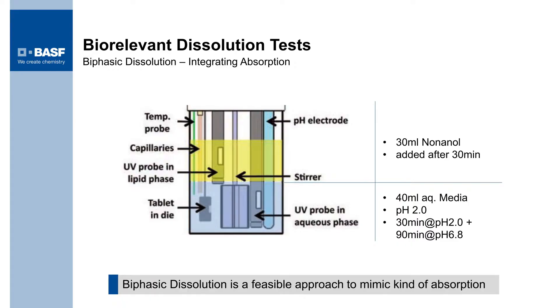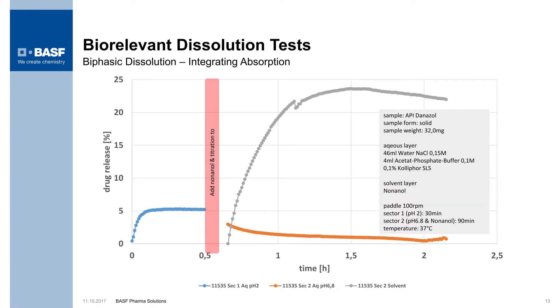Looking at bio-relevant dissolution testing, we add a second layer: an oil phase. You can use octanol, and in many cases we're using nonanol. This is added after about 30 minutes. You can measure through two different UV probes the concentration of drug in the oil phase and in the water phase under stirred conditions. Here's a quick example using a similar drug: the aqueous phase is measured up until about half an hour. At that point, the machine adds the nonanol phase and titrates it, and you can very quickly see the drug jumping into the oil phase while the aqueous phase comes back down.